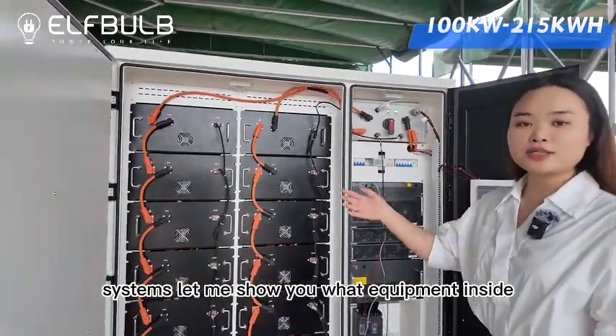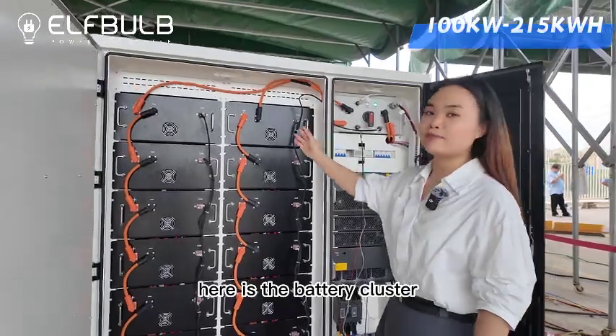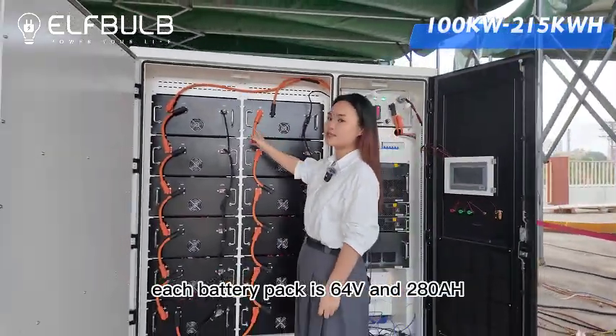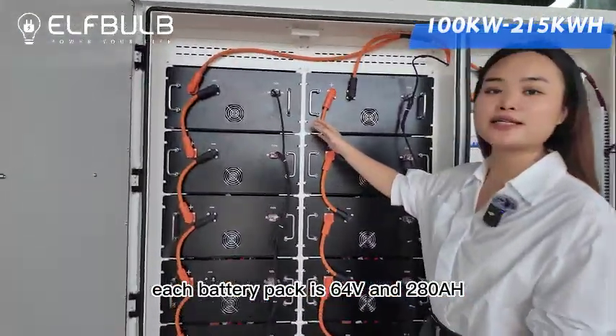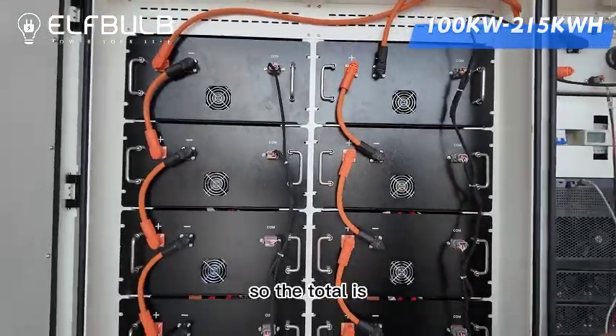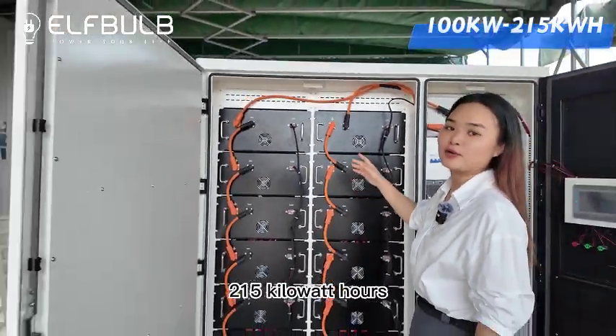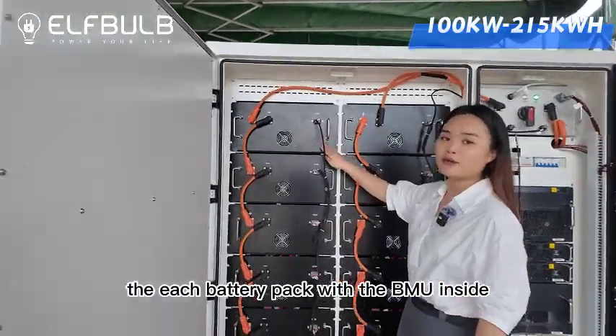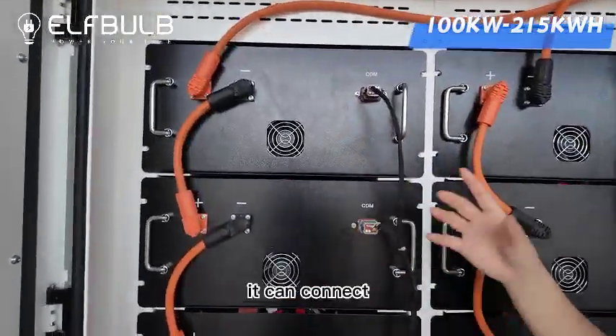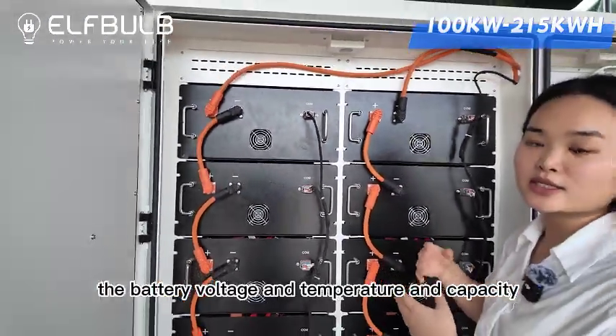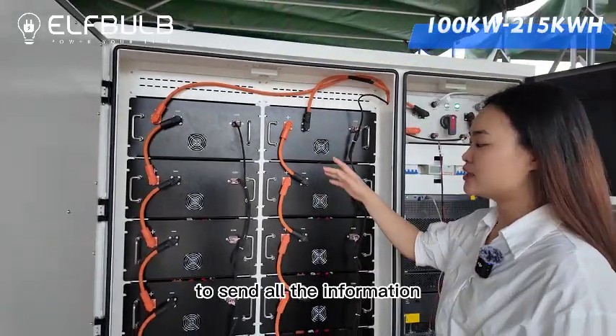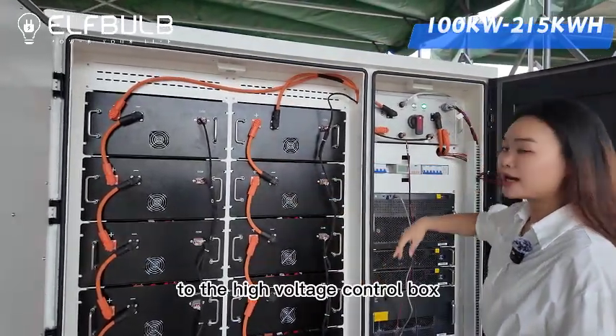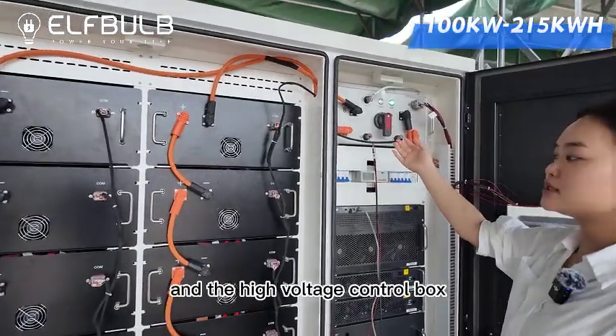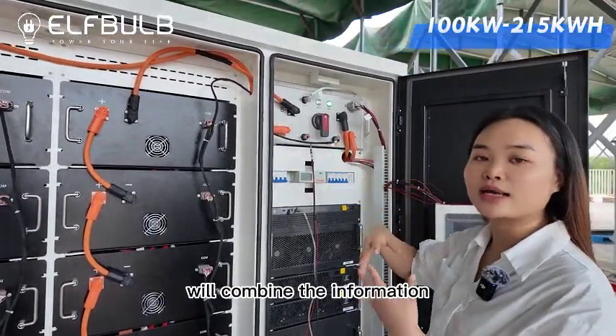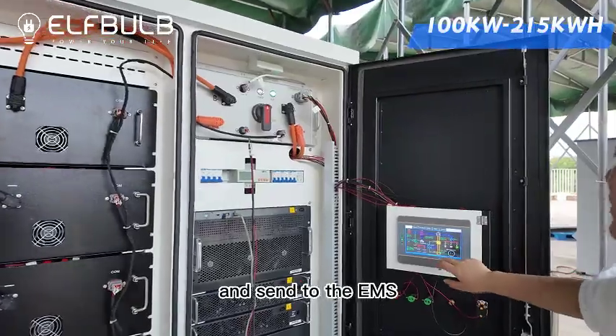Let me show you what equipment is inside. Here is a battery cluster. Each battery pack is 64 volts and 280 ampere hours, so the total is 215 kilowatt hours. Each battery pack has a BMU inside. It can collect the battery voltage, temperature and capacity and send all the information to the high voltage control box, which combines the information and sends it to the EMS.